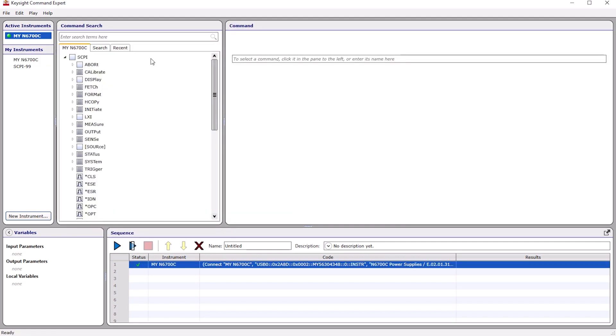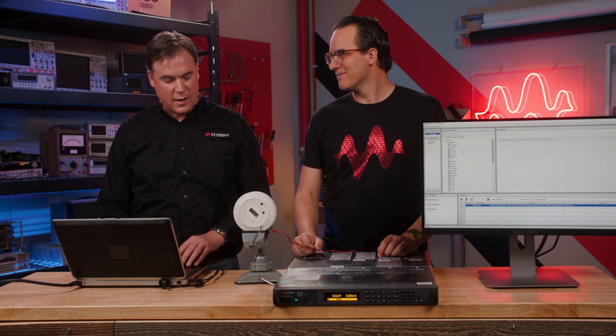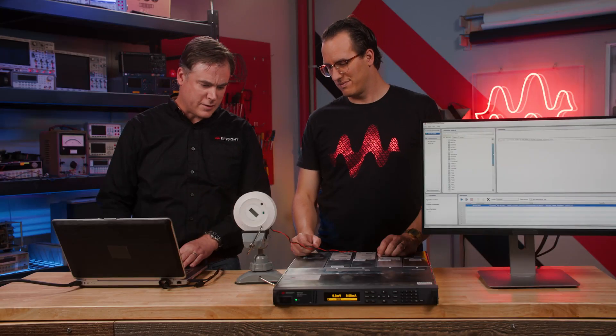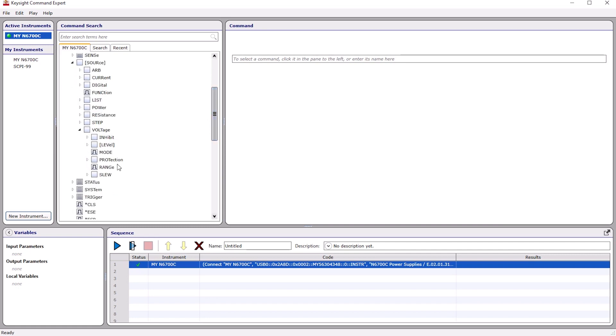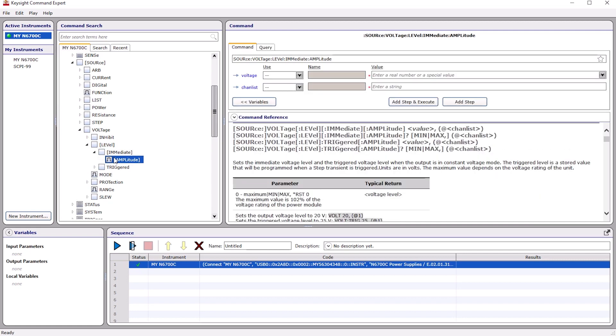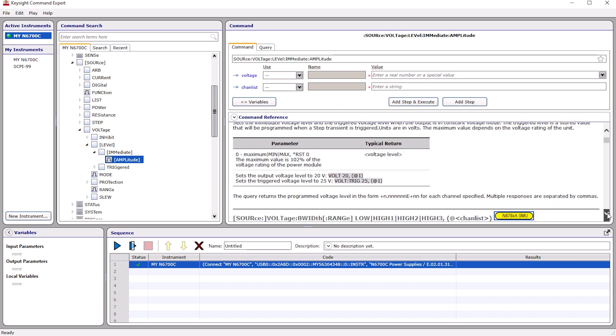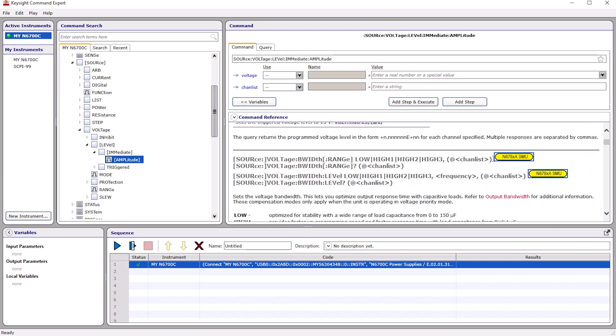Now that we're connected, you can see the complete command set for the N6700C. What I want to do is measure the current drain from this device. First, I want to set the output voltage to turn it on — since this uses CR123A batteries, that's around three volts. We go to Source > Voltage > Level > Immediate > Amplitude. Here you can see the command information — it gives a lot of details about the functionality, the parameters, and which commands work with which modules.